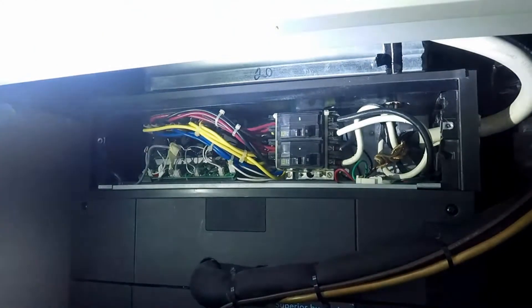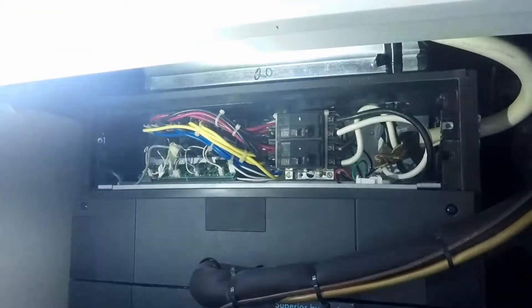Although it was very subtle, it was a problem. Since the electrical panel is correctly wired, the only place left to address is the air handler's power connections. Note, any light flicker is a problem. The lights should not flicker at all. Some electricians consider flickering acceptable. Well, not here.